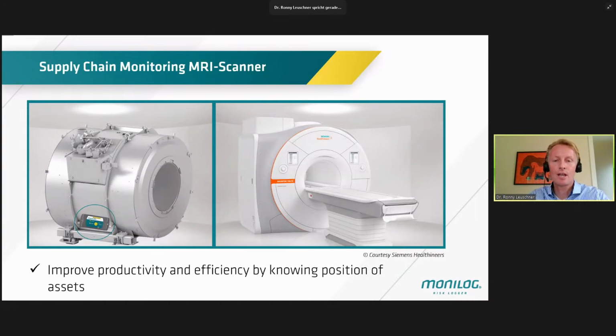A use case for monitoring a magnetic resonance tomograph. In the present case, the magnet is prefabricated at various locations distributed worldwide. Already on the way to assembly, the transport is continuously monitored in order to detect non-visible transport damages. All the inner housing parts for the liquid helium for cryogenic cooling of the coil with superconducting wires are very sensitive against external shocks or loads. Further internal installations of the vacuum vessel, for instance radiation and insulation shields and suspension elements which hold the inner vessel in position, are not visible from the outside and cannot be checked easily. In addition, these have to be as small as possible due to cost and warming.